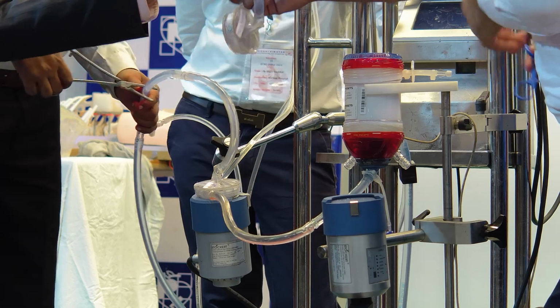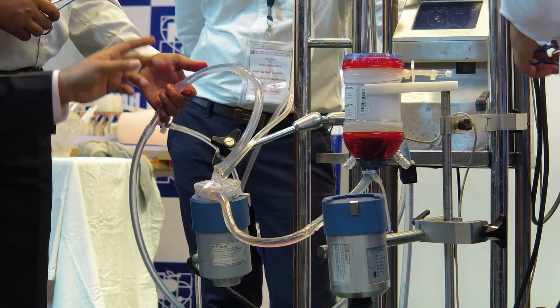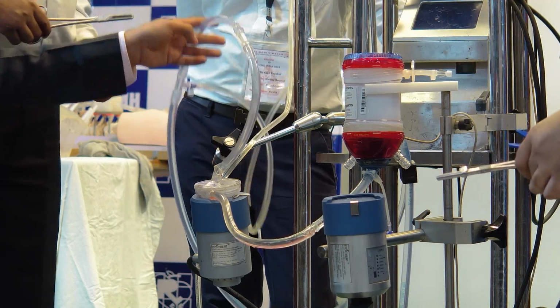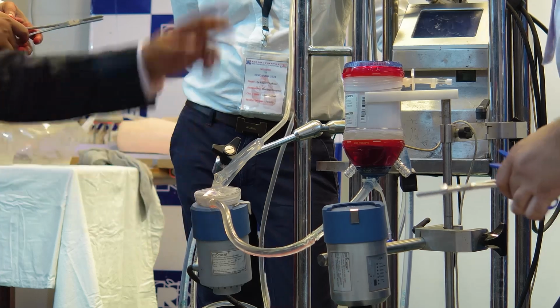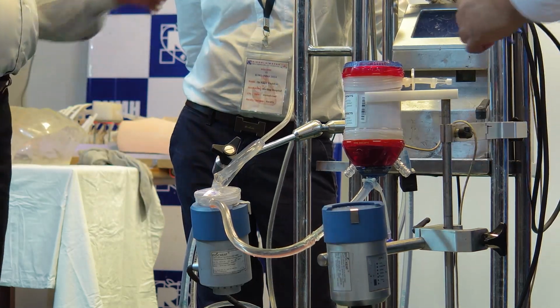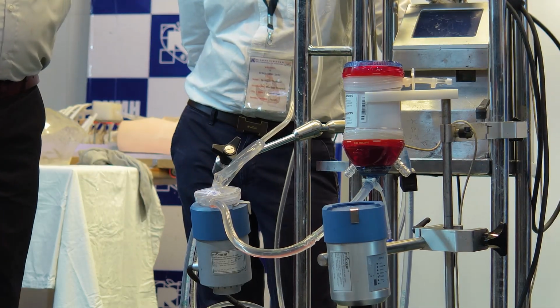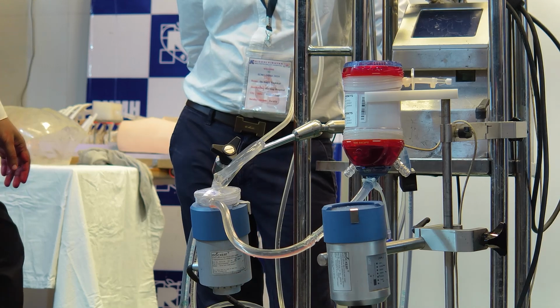Then, always when you are starting, open the venous clamp first, and last the return line clamp, after initiating the pump. That is what's required for the pump.